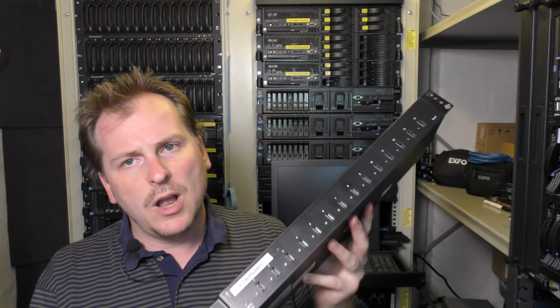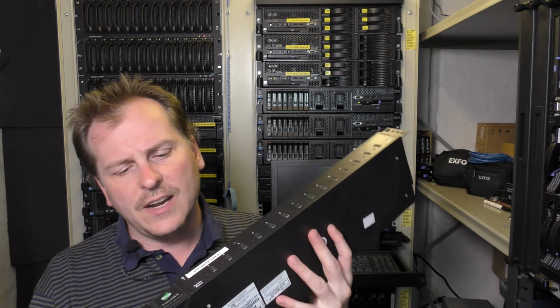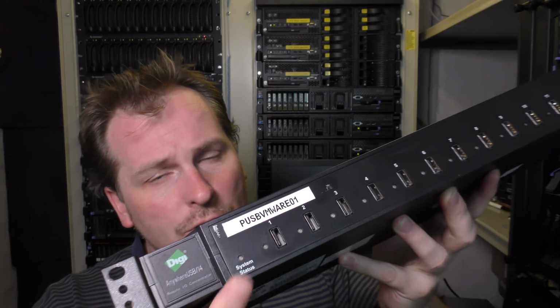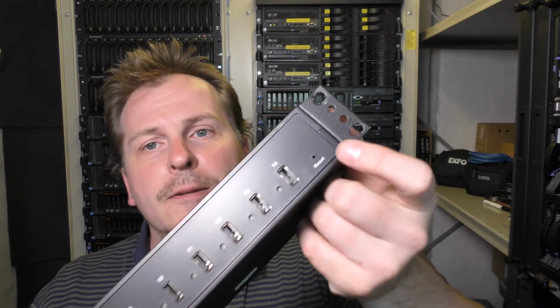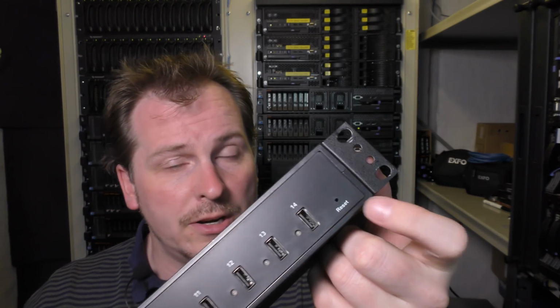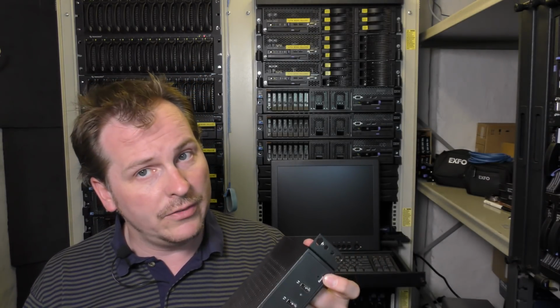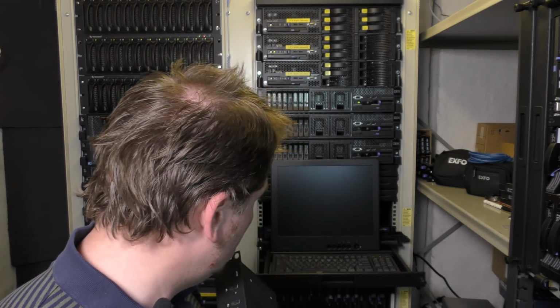I have been at the computer and found out that I think this has been in use, so we need to reset this. There is a reset button right here on the front, and according to the manual, I have to press the reset button, power on the device and count 10 seconds, and it should be reset to factory default. So let's try that. I need some power over here.